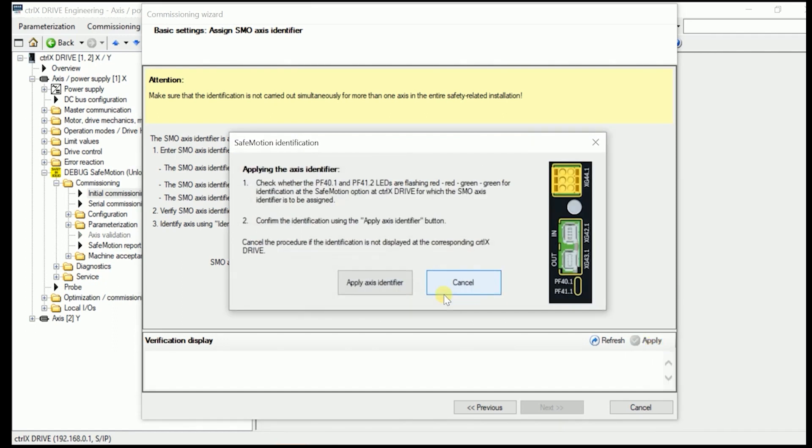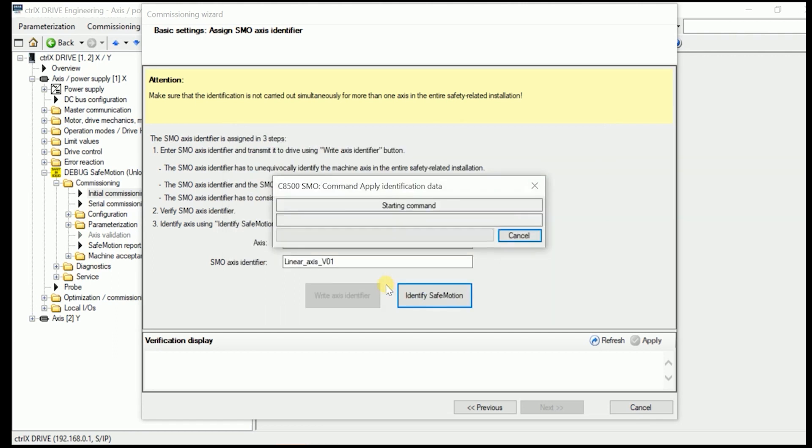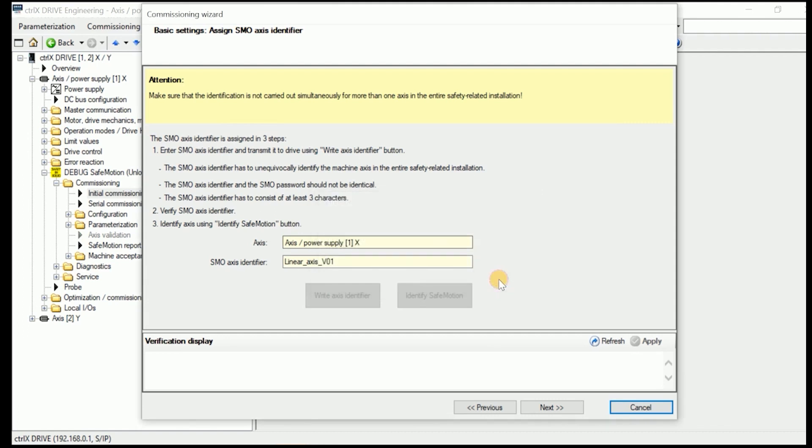Now we need to identify the Safe Motion if we are really connected to the right axis. Now directly on the axis itself, the drive, we should see a green or red always changing LED in here. If it's the right axis we are talking to, we apply the Axis Identifier. Now this assignment was successful.